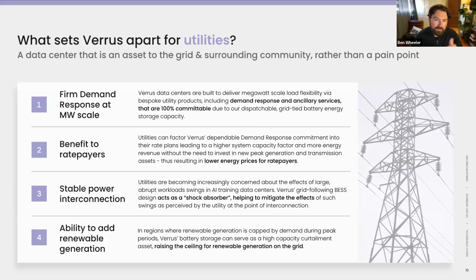That works to unlock on the customer-facing side peak shaving and other things that enable our customers to use more capacity in the data center. But on the utility-facing side, that allows us to do large scale firm demand response that's asset backed based on the battery. So that's facility level demand response where we can cut the load of the data center up to 4 hours for 50 to 100% of the load.